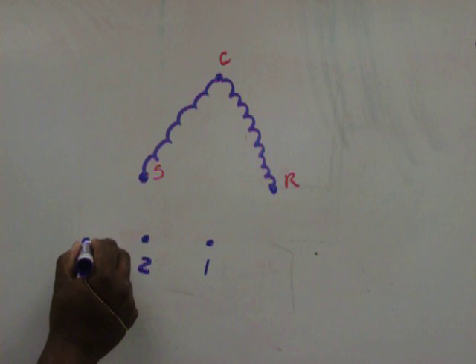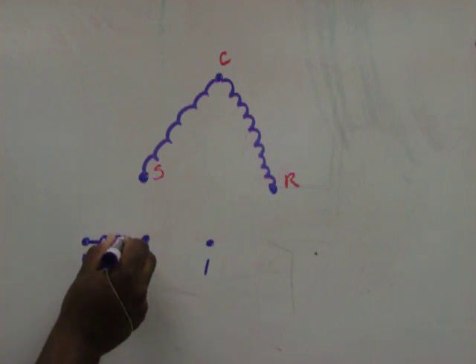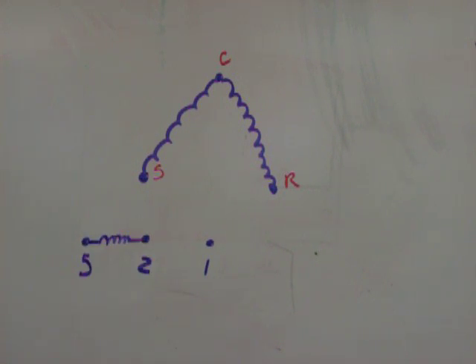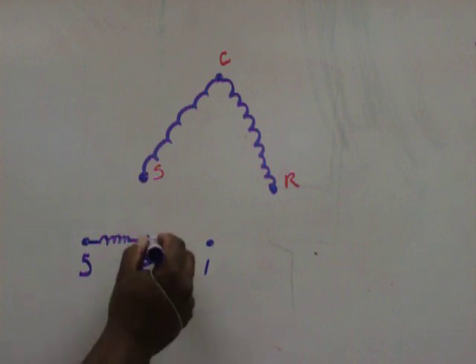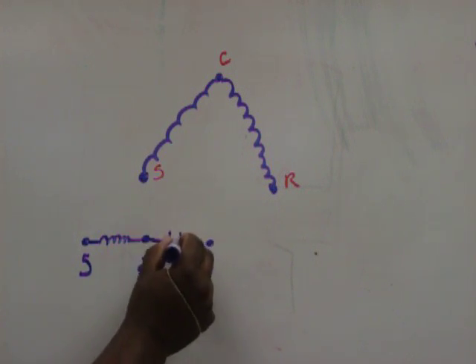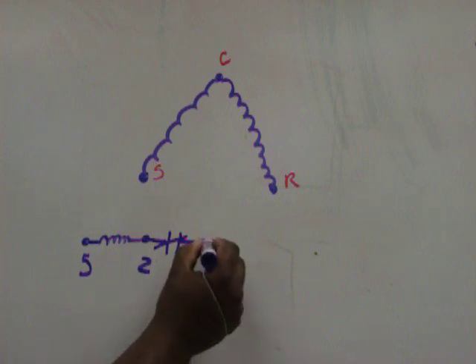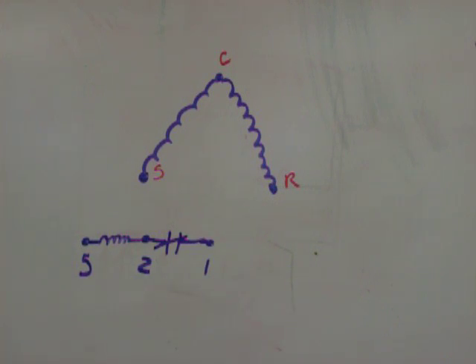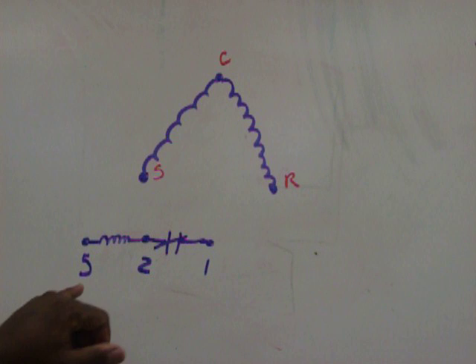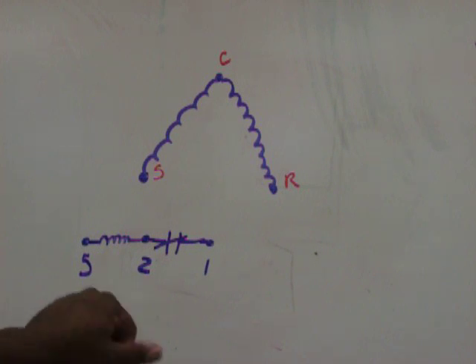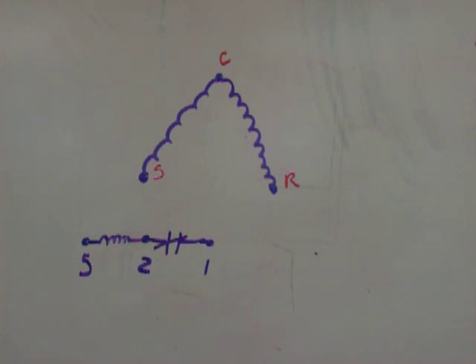In between five and two is your coil for the relay. Between two and one is a normally closed set of contacts. Remember that. Between five and two is your coil. Between two and one is your normally closed set of contacts.